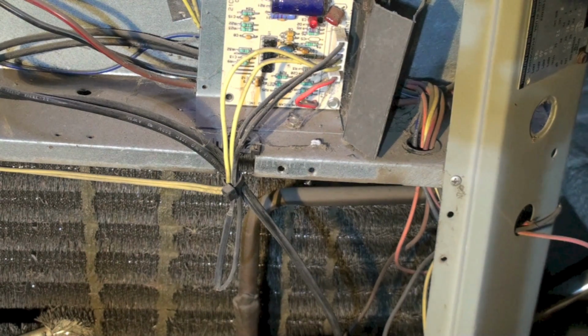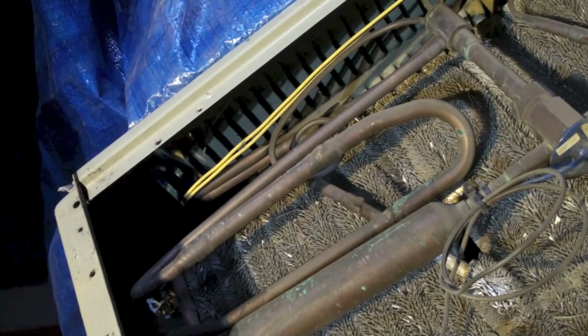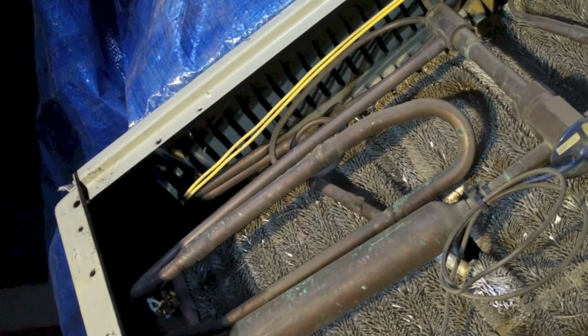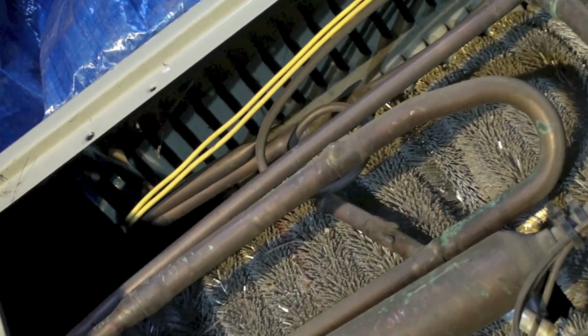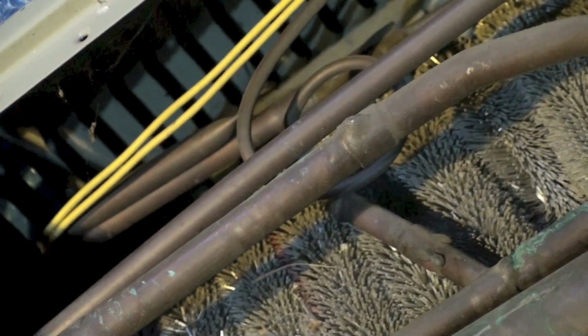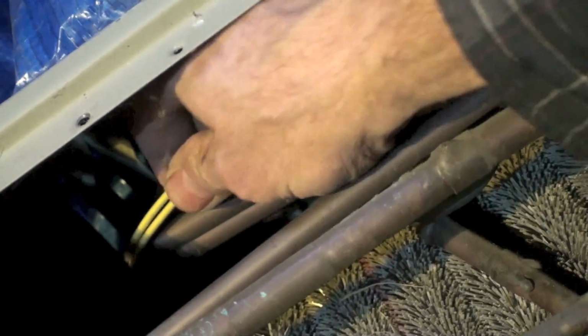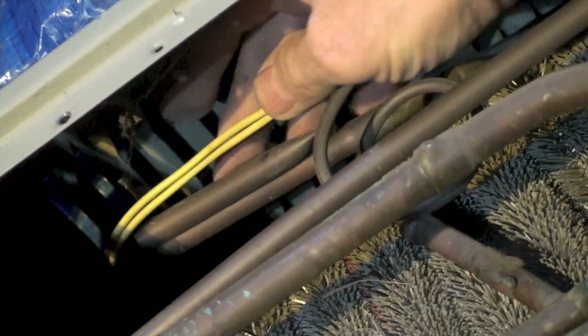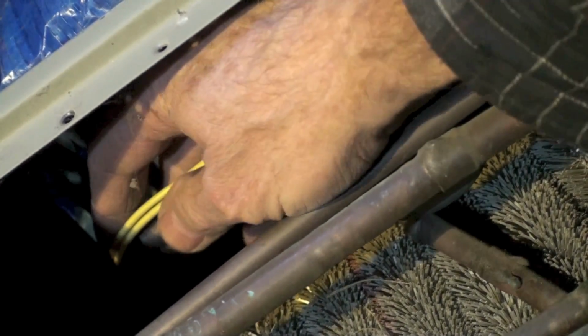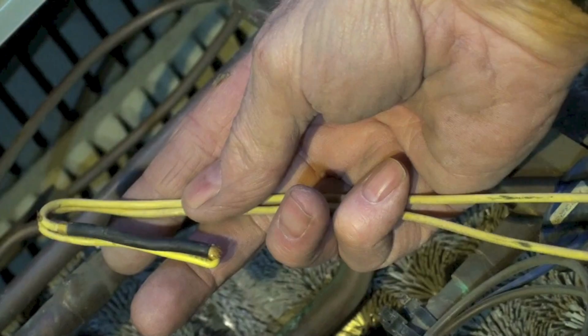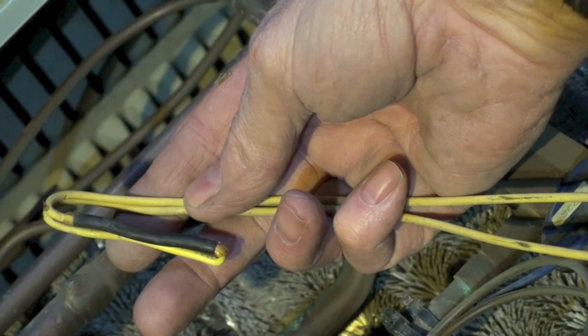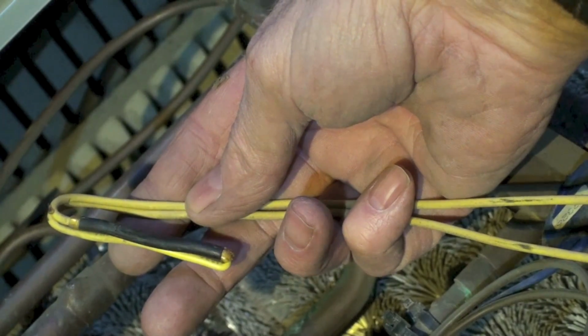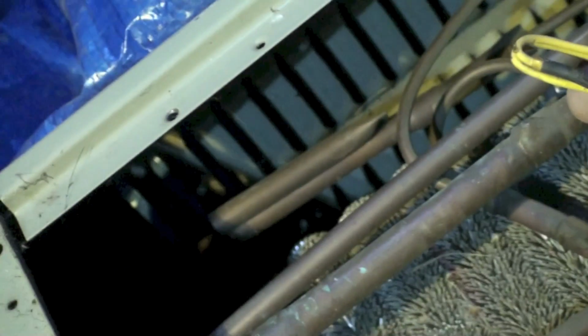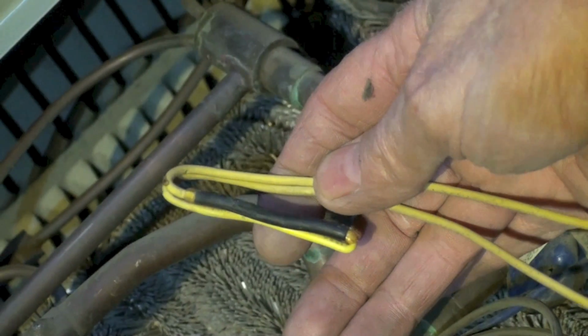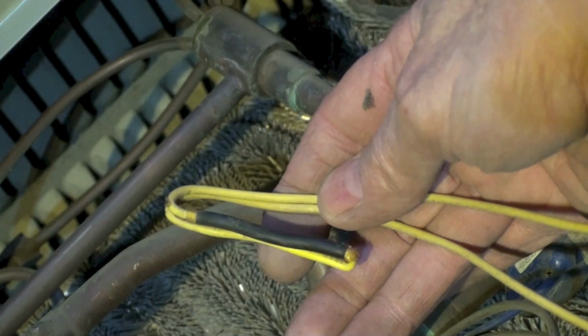I'm going to show you where that yellow one's mounted next. Okay, by following this yellow wire down, we can see where the other sensor's mounted. Now it goes right here, and it goes into this little tube. I'm going to pull that out of the tube so you can take a look at what's inside. Okay, and here's the other temperature probe here. It was just mounted inside that tubing right there. Okay, I'm going to take this whole thing off and we'll check these things out and see how they work.